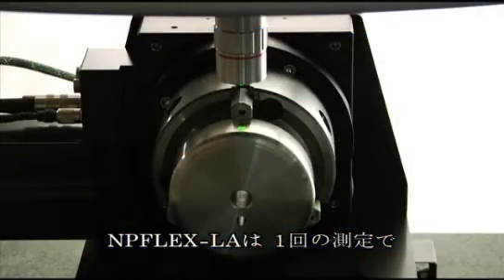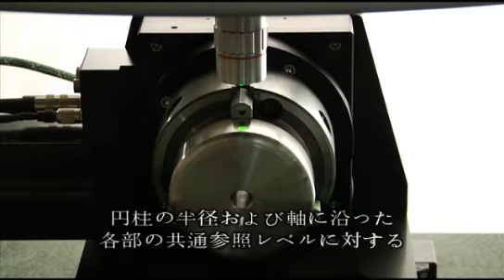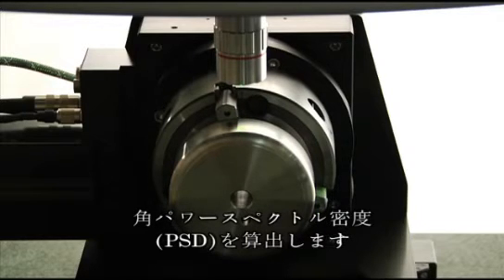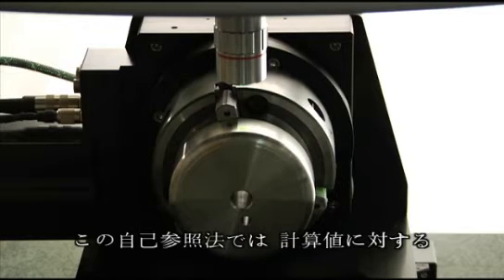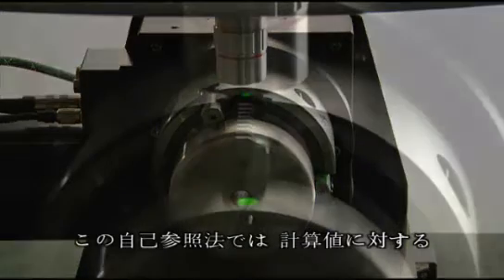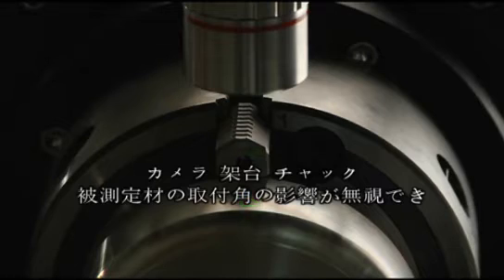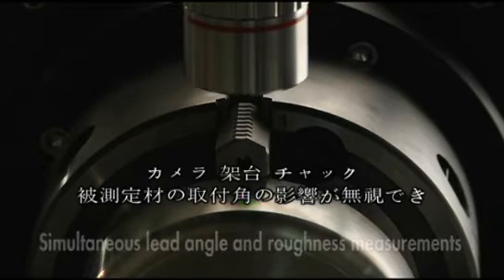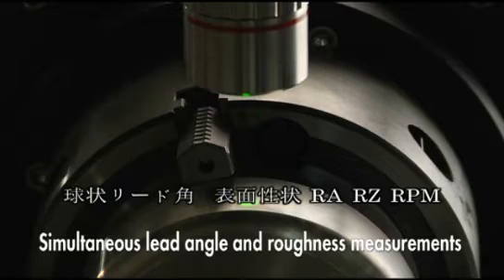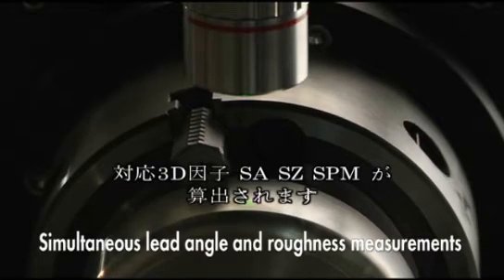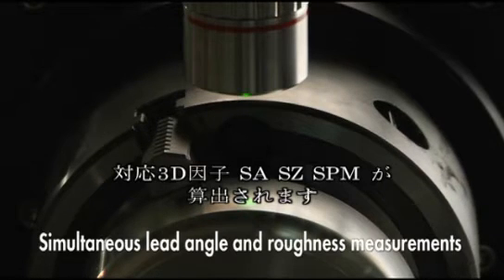During a single measurement routine, NPFLEX-LA calculates the radius of the cylinder and the angular power spectral density, or PSD, with respect to a common reference at each location along the shaft. This self-referencing method removes the influences of camera, stage, chuck, and part alignment from the calculation, reports global lead angle and both standard surface textures, Ra, Rz, Rpm, as well as the corresponding 3D parameters, Sa, Sz, and Spm.